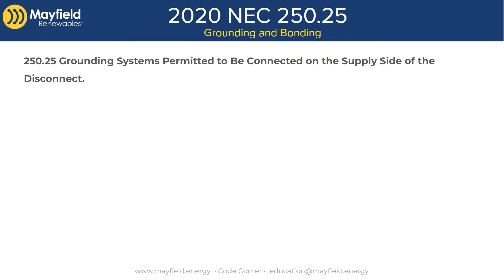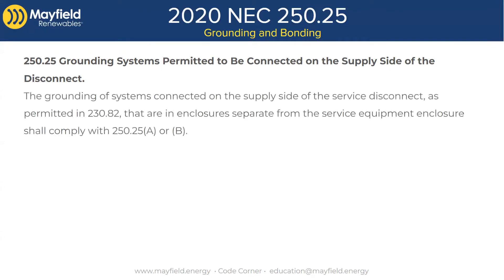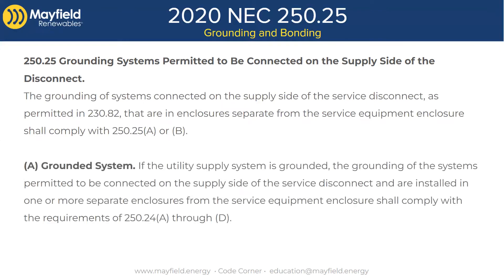The one thing that is missing — it was actually in the code until the very last moment — was some direct rules on grounding and bonding for our systems. But 250.25 is also a brand new section. The title of 250.25 is 'Grounding Systems Permitted to Be Connected on the Supply Side of the Disconnect.' So it is exactly what we were looking for — it's what we needed. It's just not in 705.11.